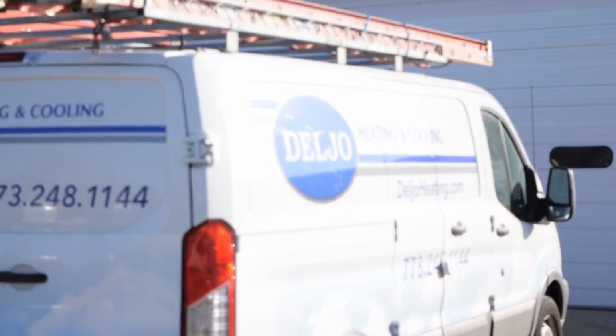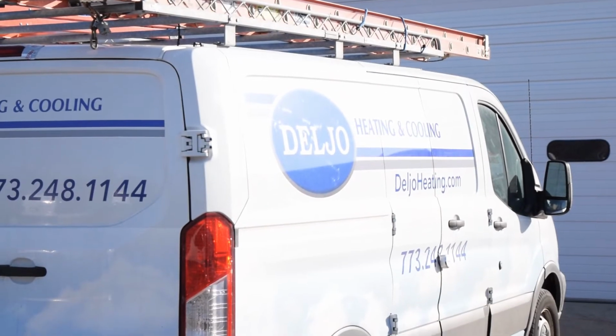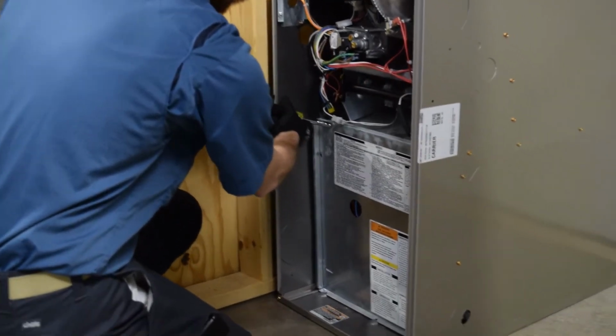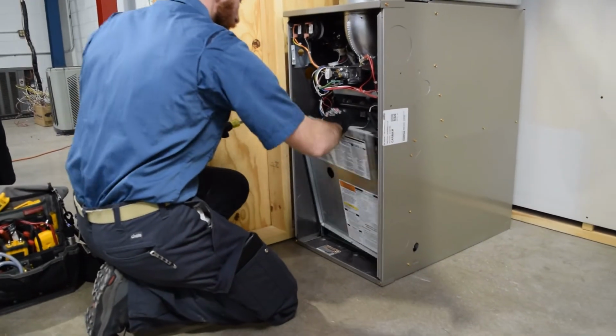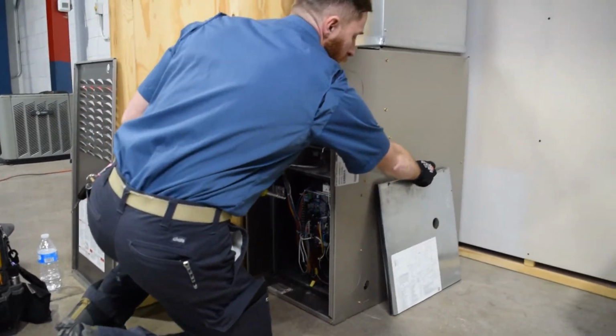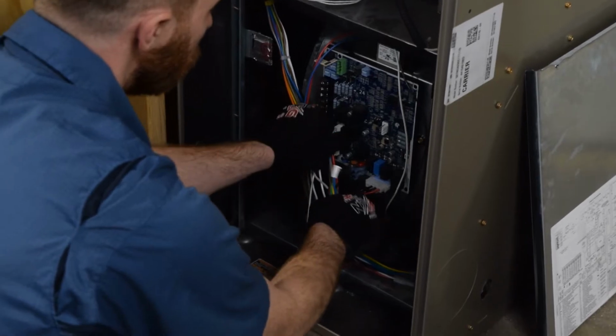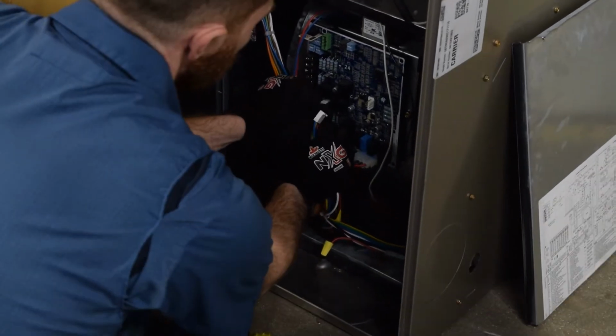What I'm going to be talking with you about today is blower wheel cleaning and why it's so essential and important to your HVAC system. The cleaning for the wheel is so important because that's the component that's moving all the air around in your home. The major components that it's putting stress on are the blower motor itself, the heat exchanger, the evaporator coil, and all ductwork associated with that system. You're losing possibly up to 30% of airflow.